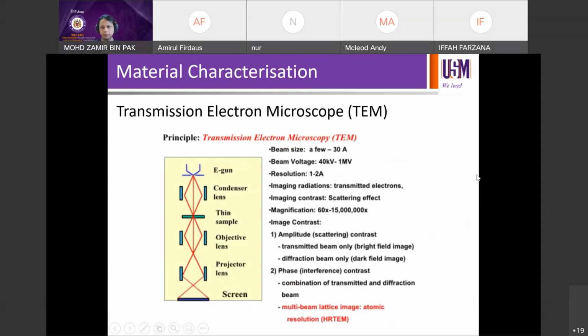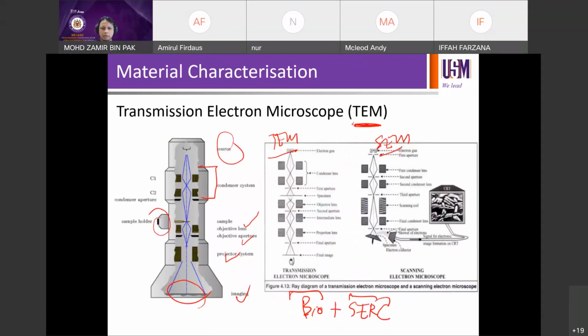Okay, so the typical settings that we use in TEM: beam size of about 30 angstroms, and then beam voltage depending on the samples and resolution, but it's based on transmitted electrons. If you use SEM, you're going to get your image based on, say, this is your sample. Your sample will be reflecting and scattering the electron beam, not light, and the electron beam will be detected. So it's based on scattering. Scattering, back scattering, is the principle, but TEM is based on transmitted electrons.